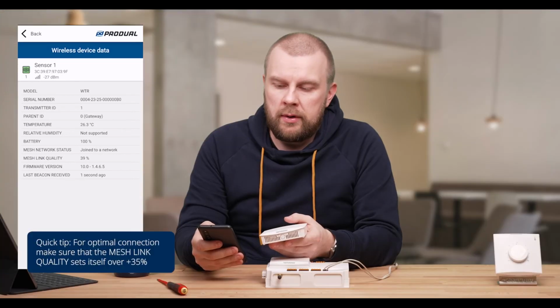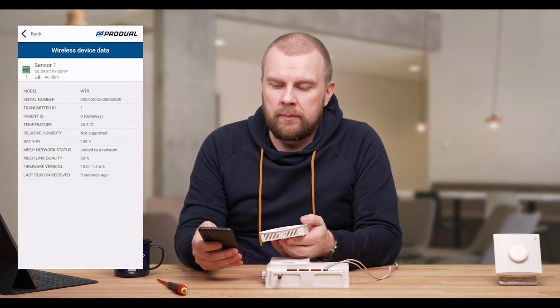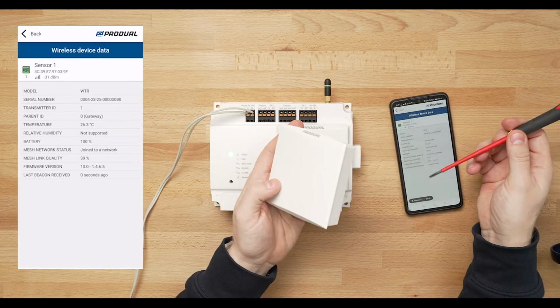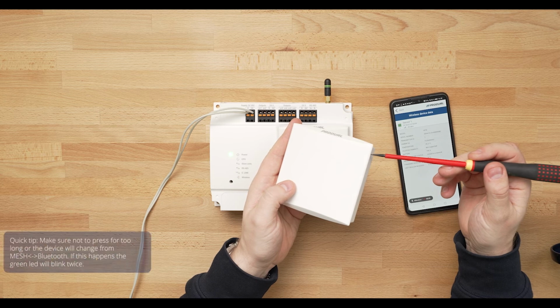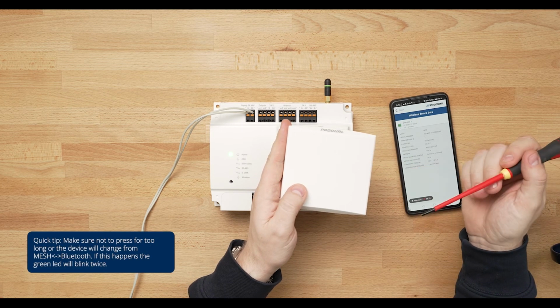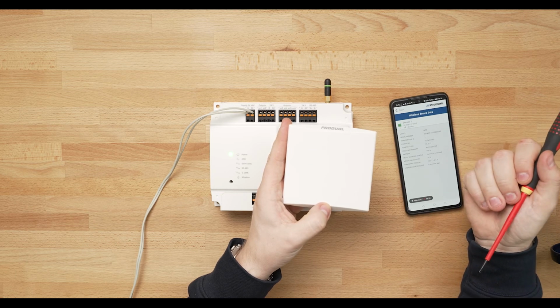After the 1 hour, the WTR is turning off the Bluetooth beacon and data cannot be read anymore. If there is a need to read data later on, this can be activated by pushing the button on the side of the WTR. To activate the beacon data back on the WTR, you need to push the side button a little bit, under 1 second. It will blink the green LED once and then the blue LED starts to blink. This will tell you that the beacon mode is on.